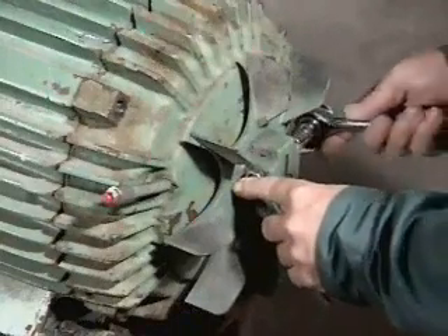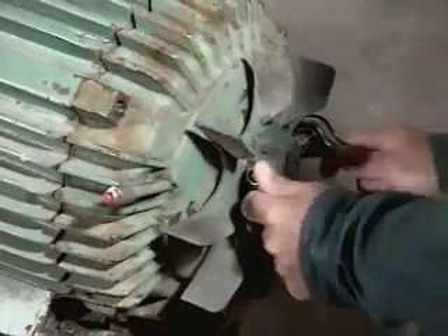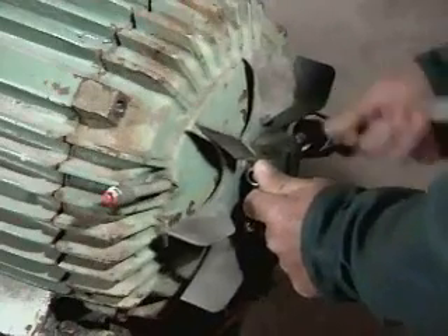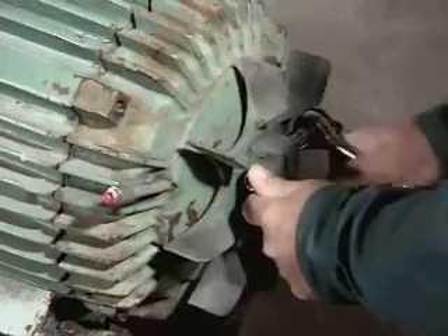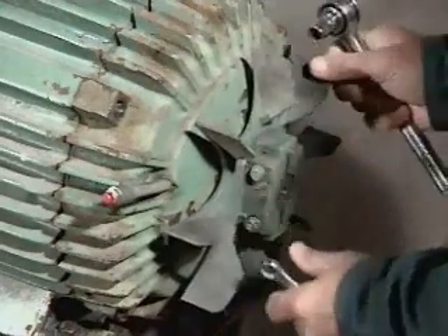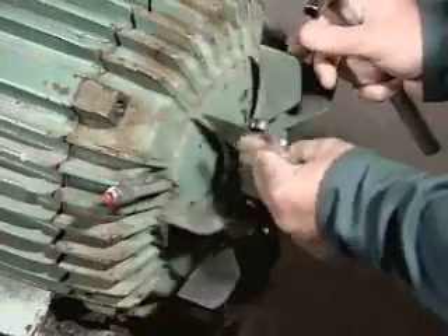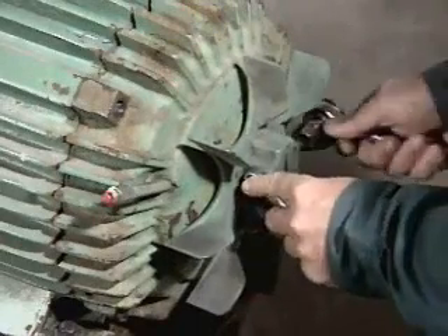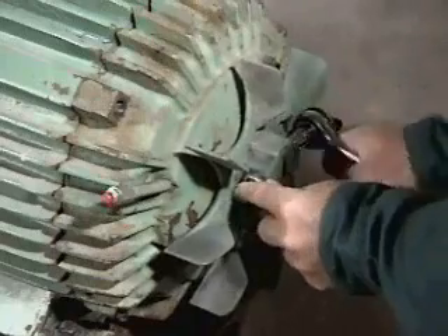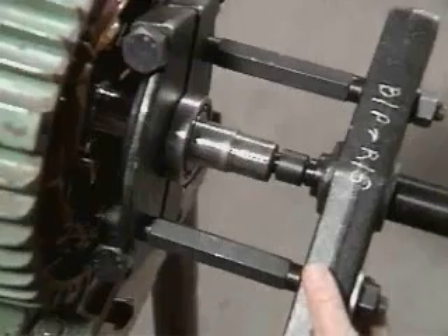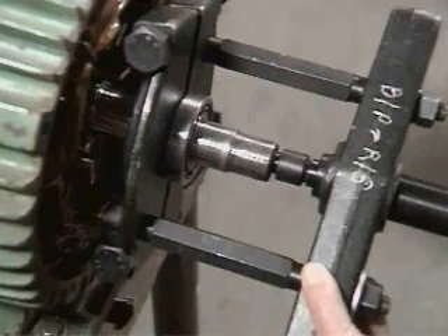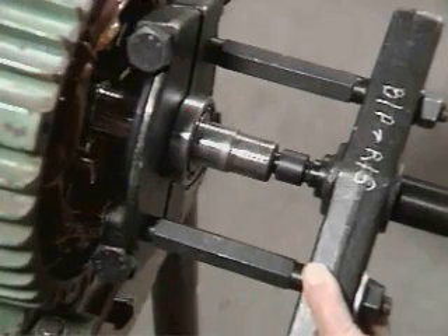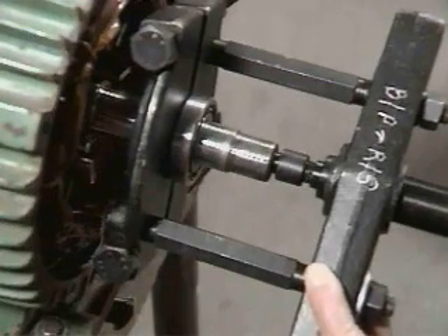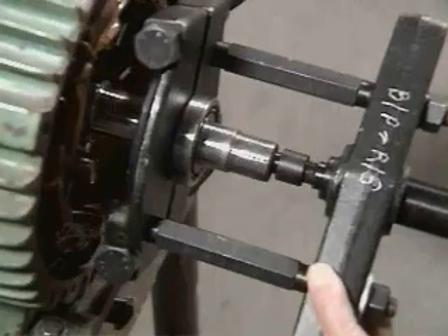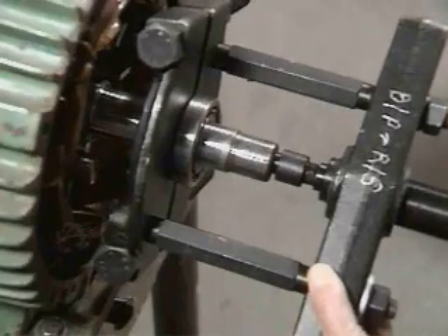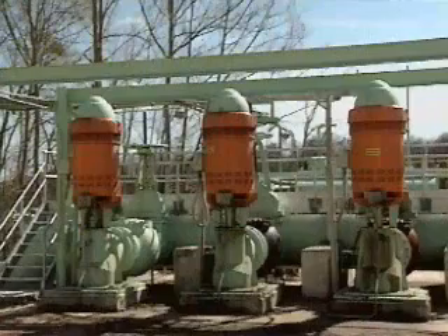Periodic motor maintenance is maintenance that is done on a regularly scheduled basis, usually in a shop after disassembling the motor. The purpose of periodic maintenance is to run tests on the motor, clean the interior, and inspect and lubricate parts. Corrective motor maintenance is maintenance that is done as needed to correct problems that were identified during the preventive and periodic maintenance checks. Select Next to continue.